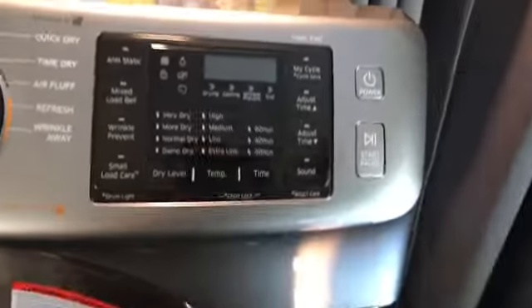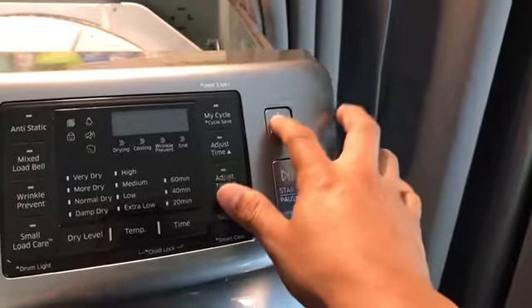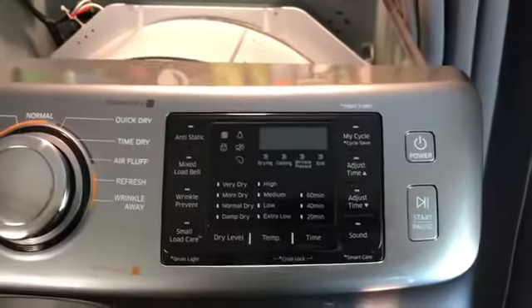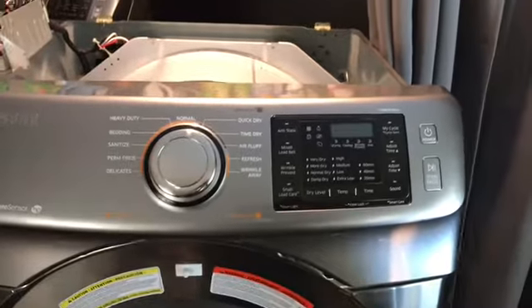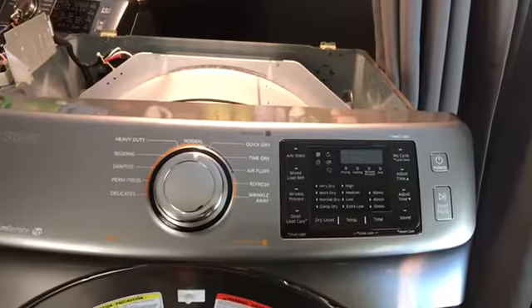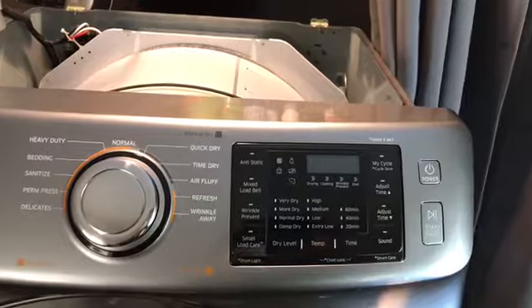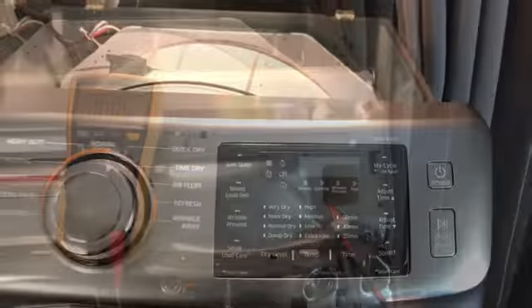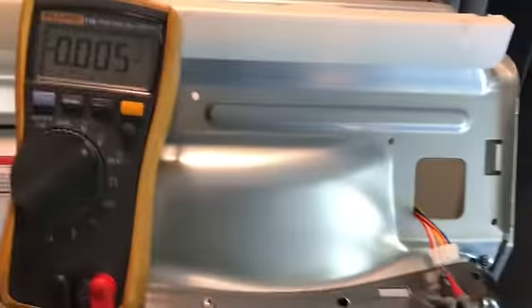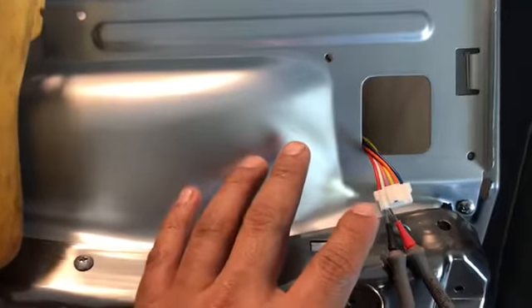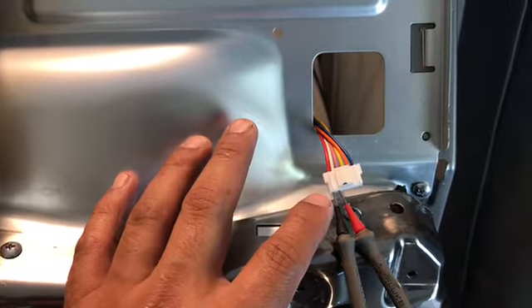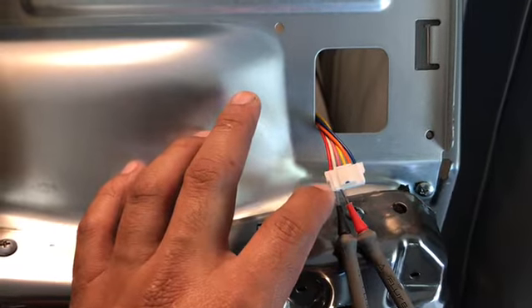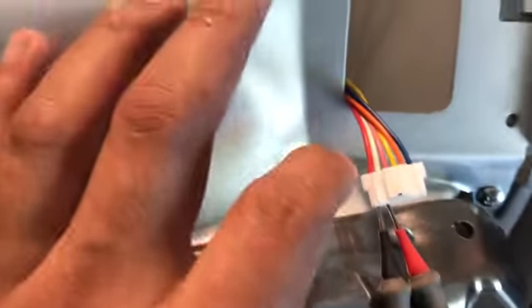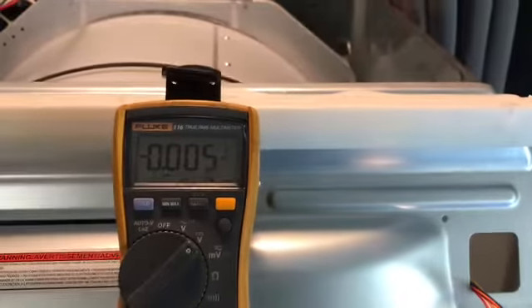So how do we check this voltage DC to the display? We're gonna go ahead and disconnect this display, and we'll put our leads to the wires that need to carry voltage to power up this display. Pins 5 and 6 would be the ones that carry the voltage from the main board this way. We'd have to be getting approximately 11 to 13 volts DC from pin 5 and 6, which is the orange and the white. We have 0.